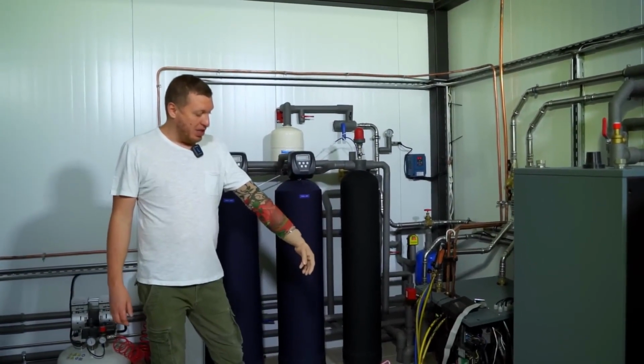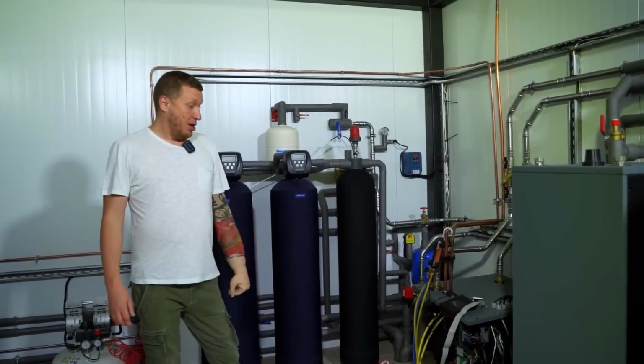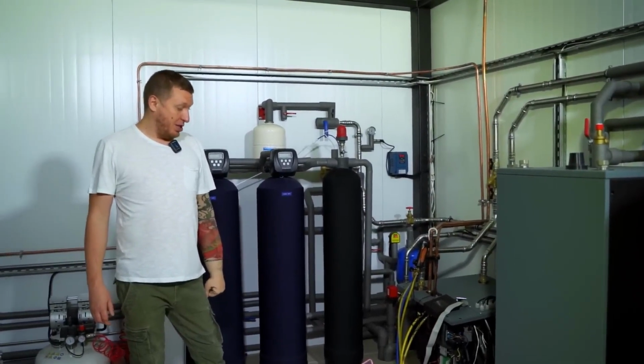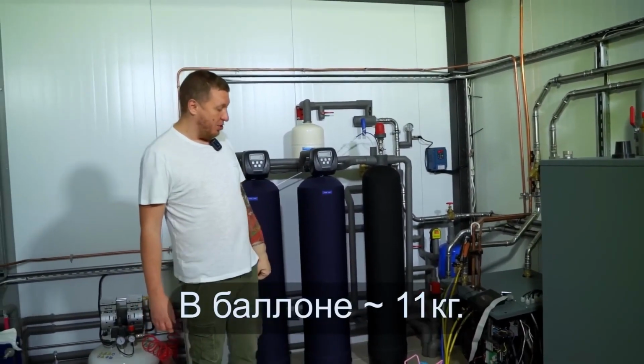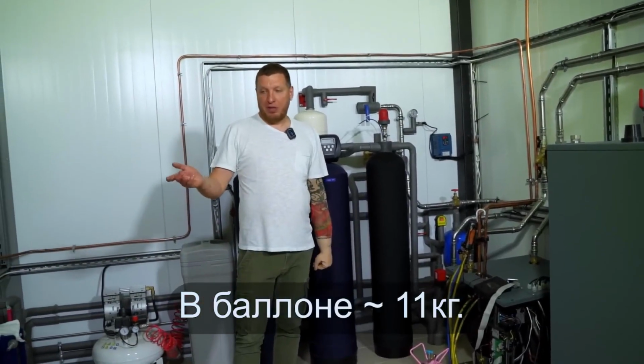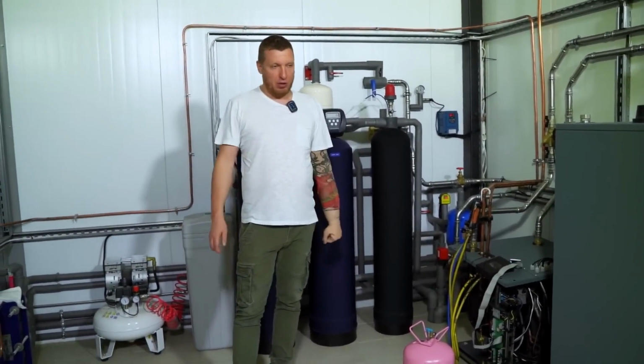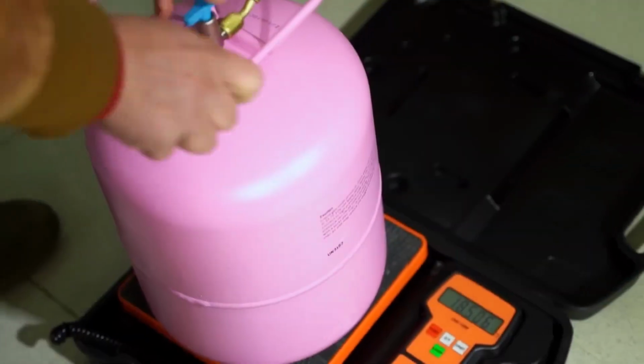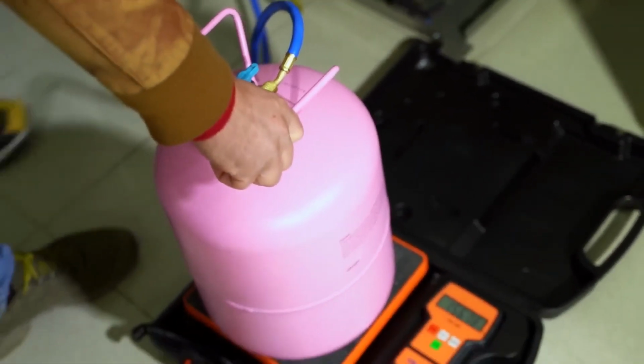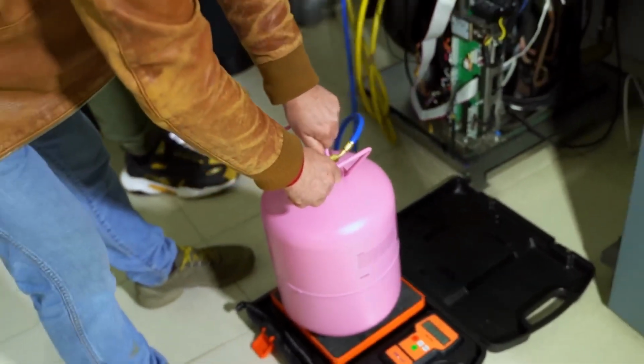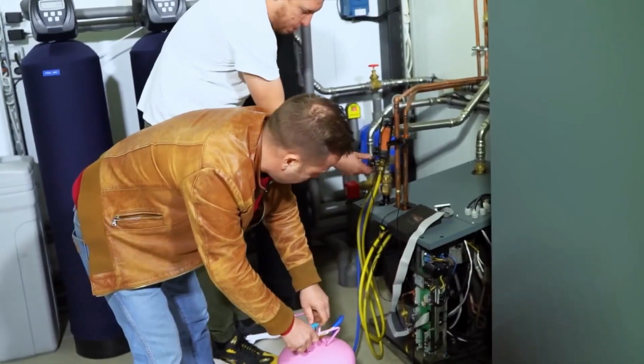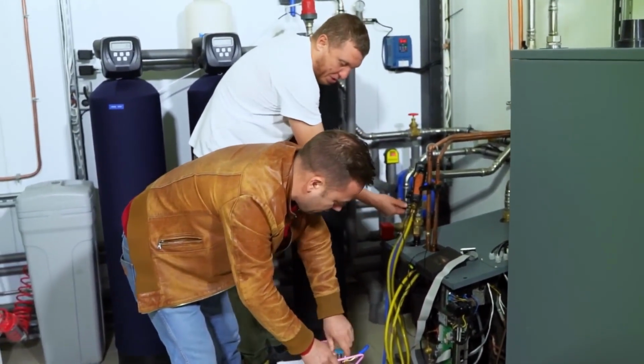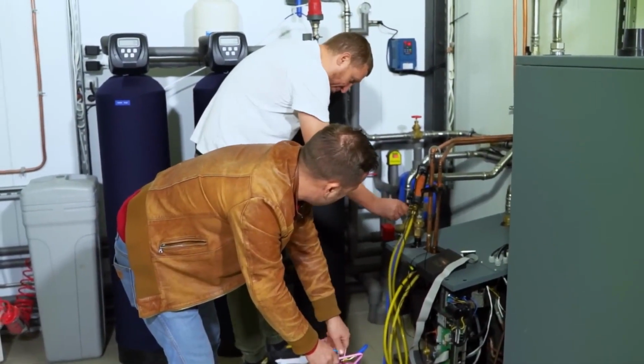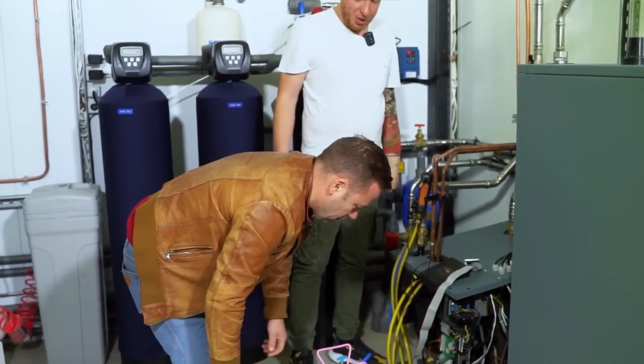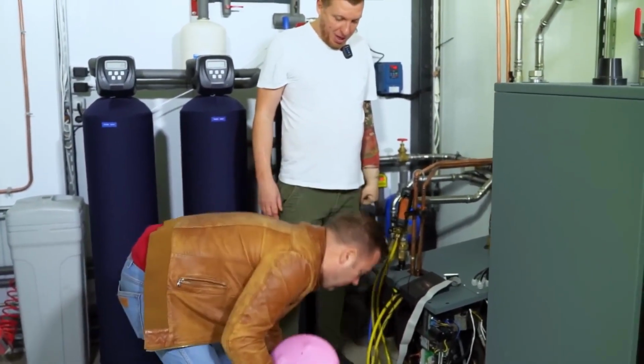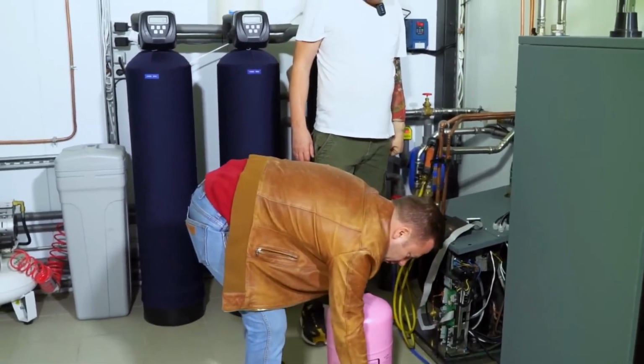The heat pump runs on R410 refrigerant. It has gotten more expensive now, about 10 to 11,000 rubles per cylinder. A lot of refrigerant had to be pumped into this circuit because of the large condenser, about 40 kilograms. We tightened special springs. Alright, I'll blow it out now. We need to blow out this monolithic system. We adjusted the refrigerant a lot. It's fine, there's no air left in there. Turn it over. This is how it's filled through the liquid phase.